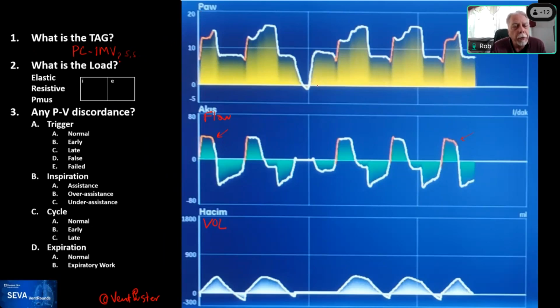So any way you look at it, it's pressure control plus, as you pointed out, there is this expiratory flow during the set inspiratory time that can only happen, to my knowledge, with an active exhalation valve in a pressure control mode. So despite the fact that this is a very chaotic pressure and flow waveform, there are enough clues that we can make the distinction. I think it's important to note that there are pretty clearly two kinds of breaths: spontaneous 1 and 6, and mandatory is the rest. So that's some kind of IMV.